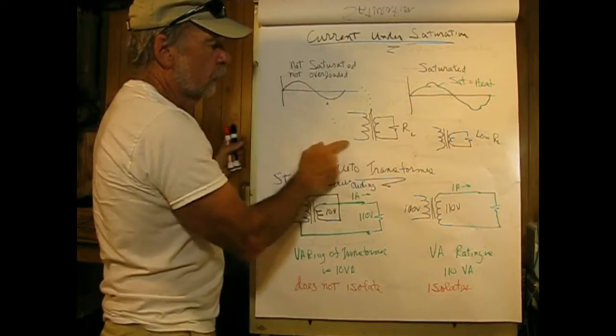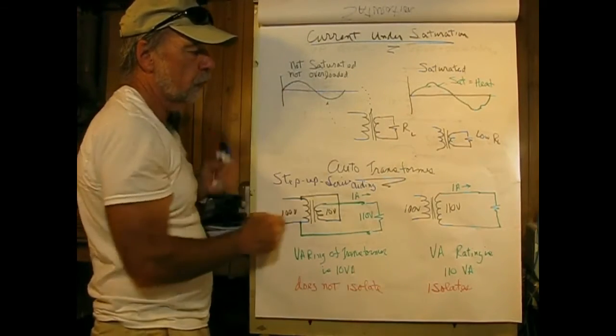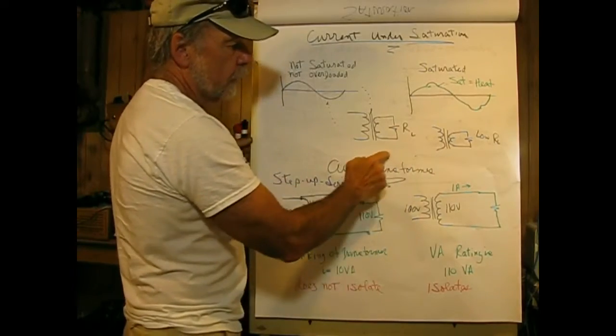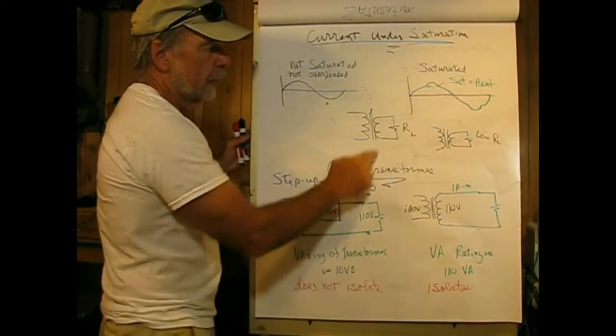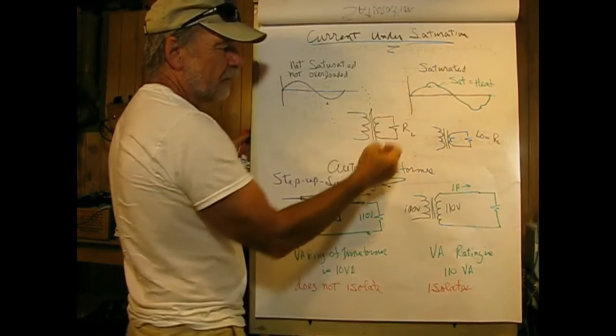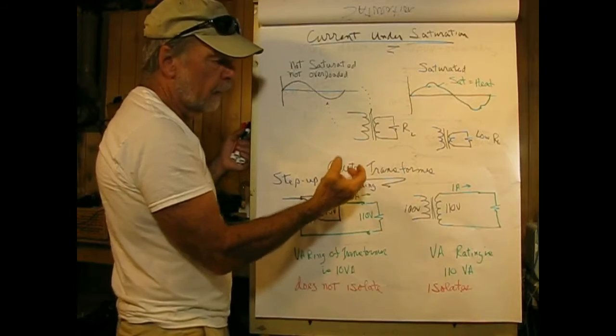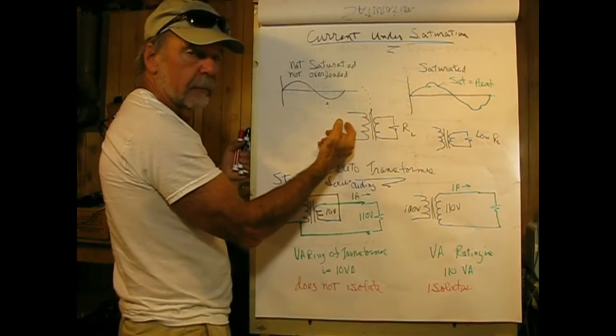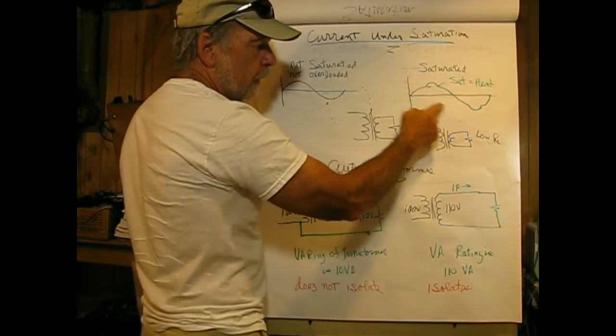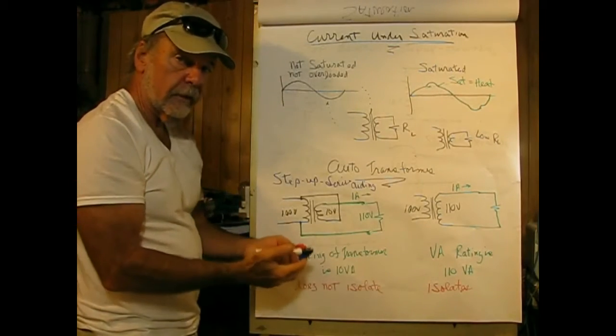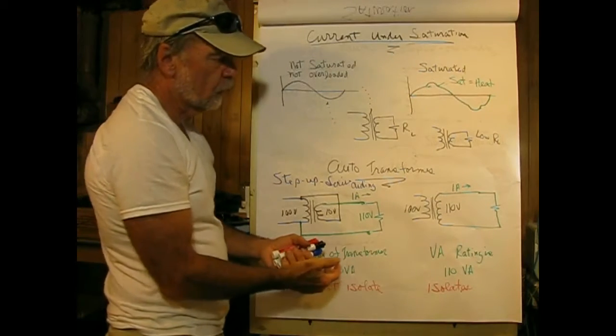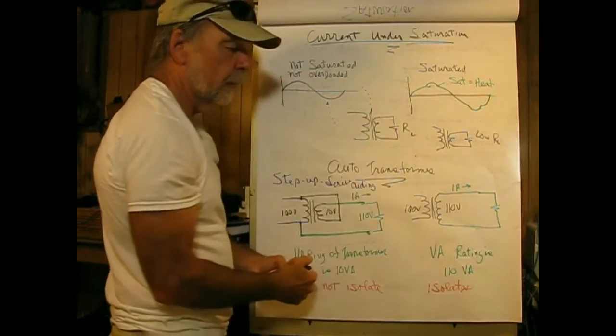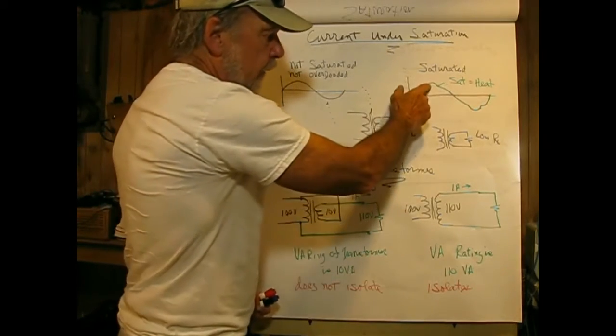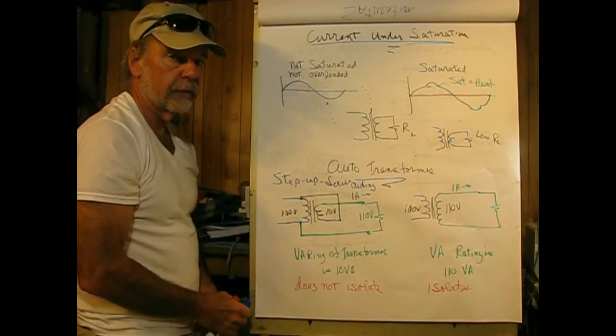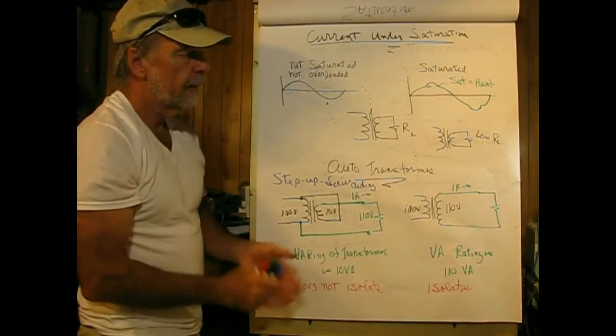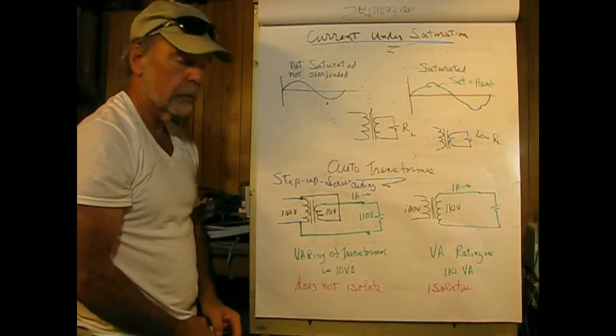Take a look at a transformer that's not overloaded - the current's sinusoidal. Now if we saturate this, with low load resistance, when it hits saturation the flux doesn't increase, it doesn't change. Therefore there's no changing flux to further inhibit current flow, and the current gets these little bumps on top of it. That increases the heat in the transformer. We'll make more sense of why this happens in a minute, but for now, that's a very bad current to have. If you see that, you have to put a resistor in and look at it - it indicates that the transformer is overloaded.